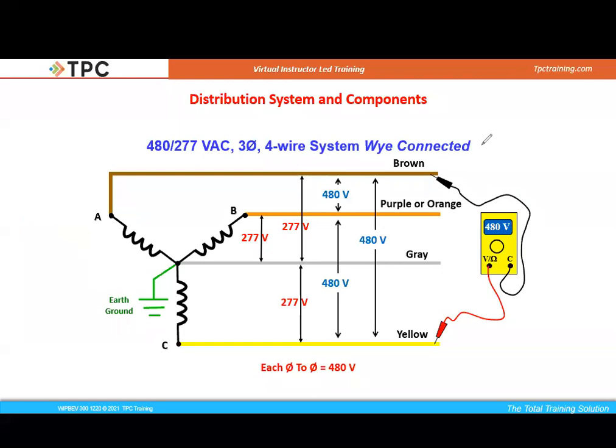One is the color code is kind of important. So as long as we have wired in accordance with how we've installed this over history, and so time has evolved us to the point where this is the color code widely accepted for three-phase here in the United States, and it was for a long time brown, orange, yellow. That would signify 480 volts. And so in the National Electrical Code in 110.15, they have now utilized the orange color for something a little bit different, which is going to be a high leg delta, which I'll explain in a second. But now you might see purple out there, but a lot of people are still using brown, orange, yellow. So that's no problem. But they should identify that and let us know that those colors mean three phase 480.